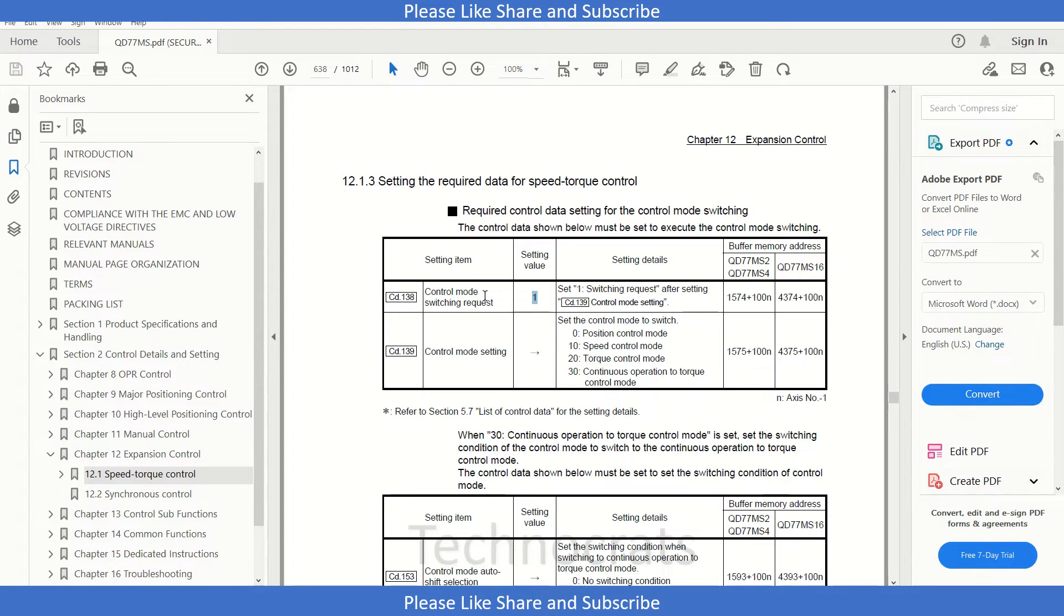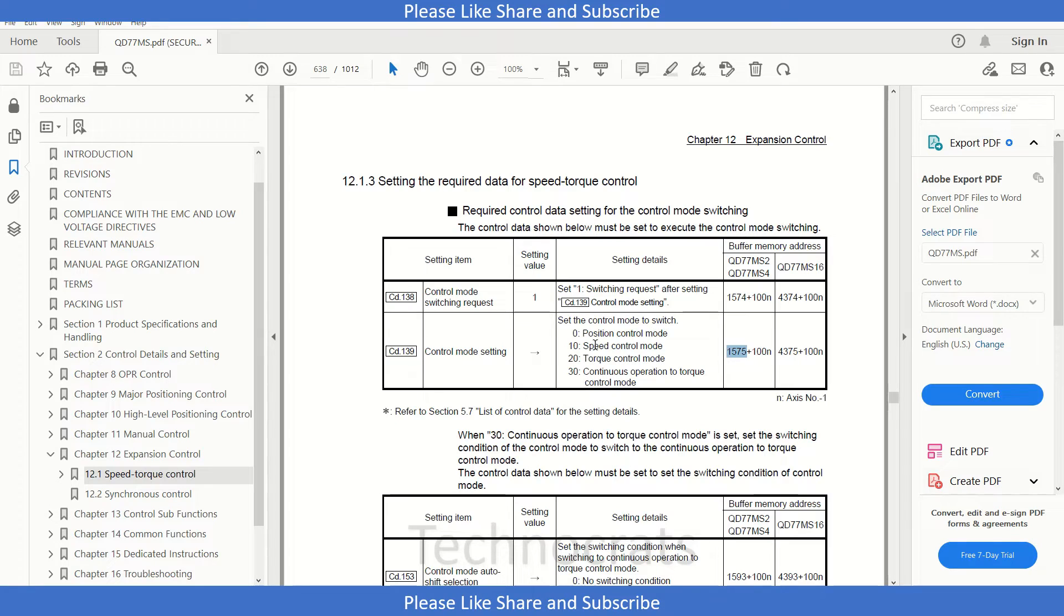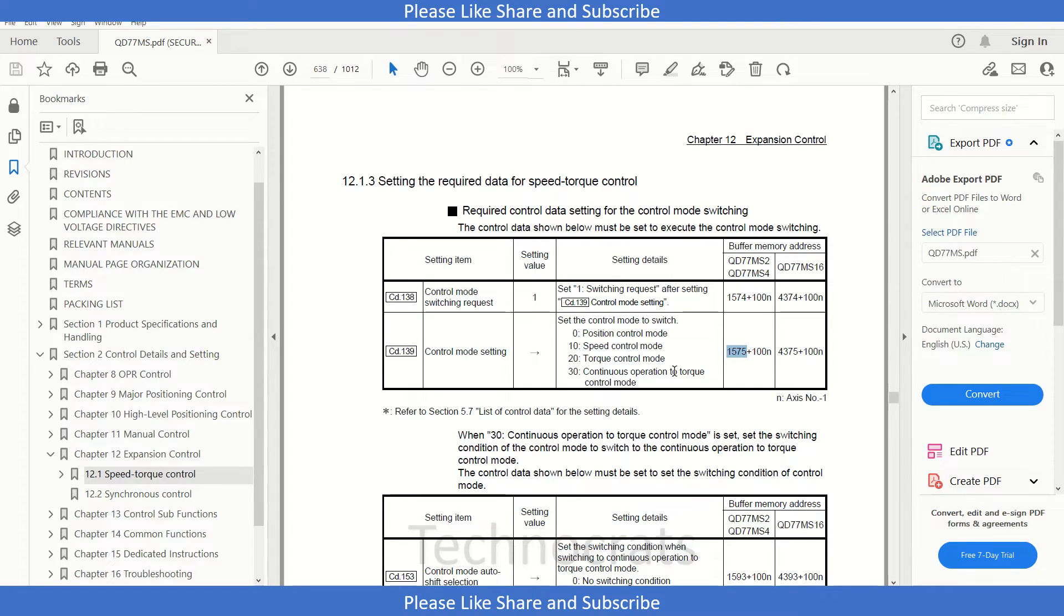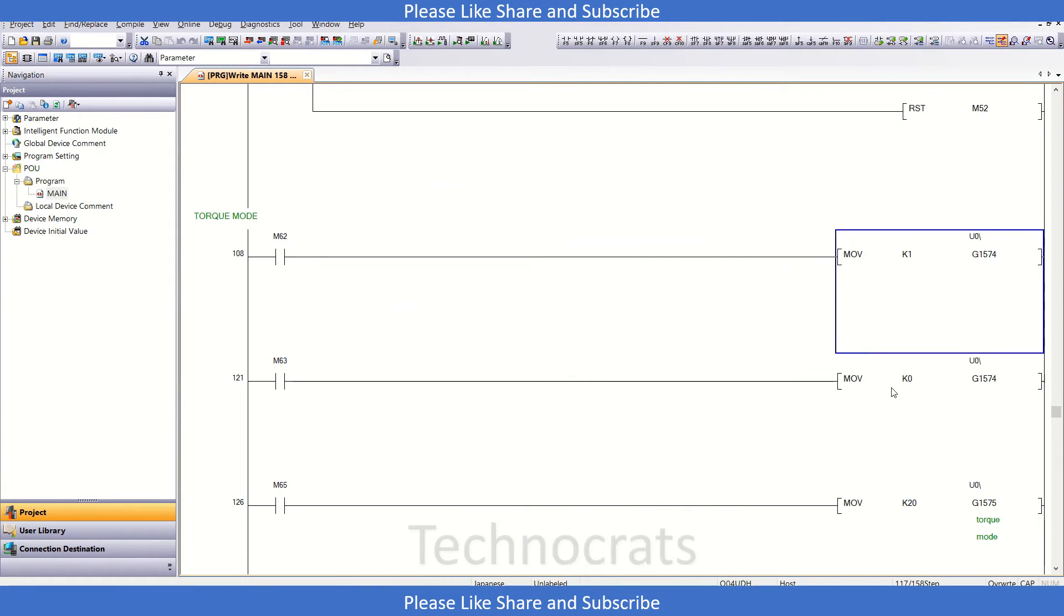The other one is 1575 buffer register. That is for control mode setting. If it is 0, then position control mode; 10 is speed control mode; 20 is for torque control mode. And that is for continuous operation to torque control mode. In here in the program, I have used K20.